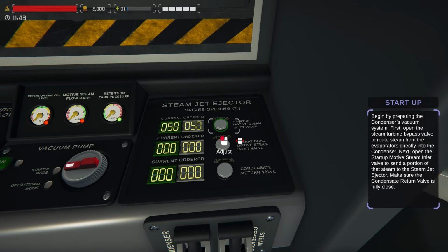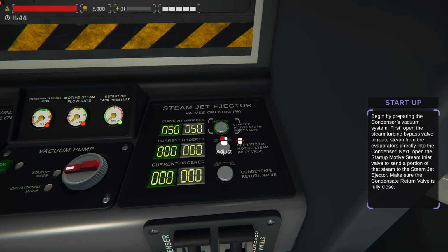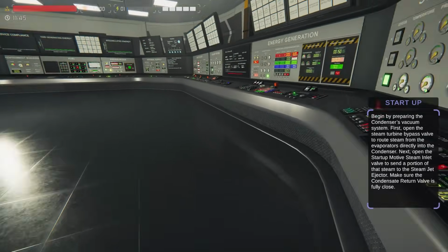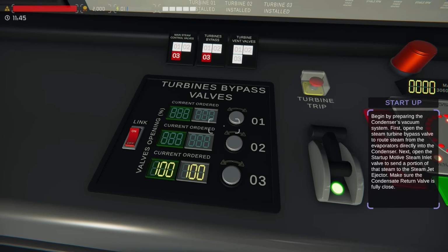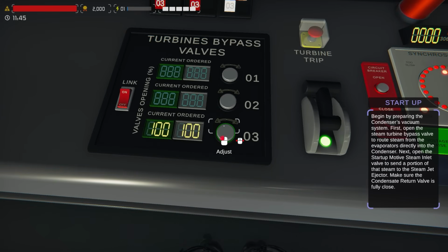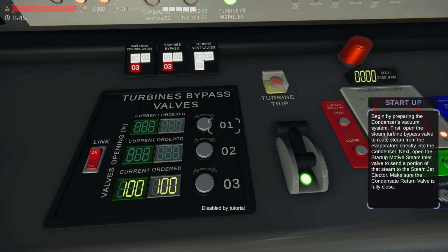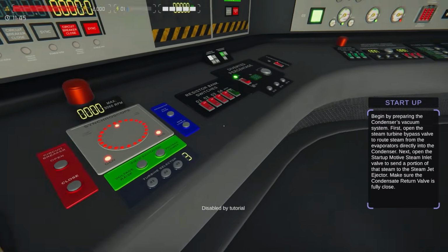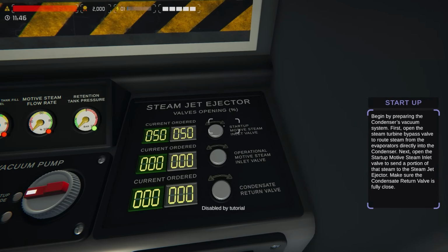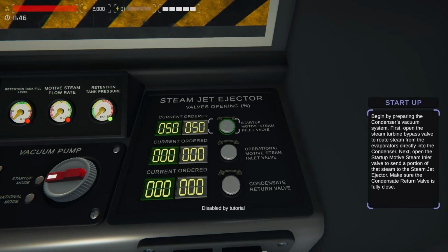Right. Do I need to alter anything? So I'm going to double check the tutorial. I said I was going to have to probably go through this one again. Firstly, open the steam turbine bypass valve to route steam from the evaporators directly to condenser. So, turbine bypass valve. Yes. Done. I can't alter the one? No, I can't. Right, next open the startup motive steam inlet valve. Startup motive steam inlet valve.